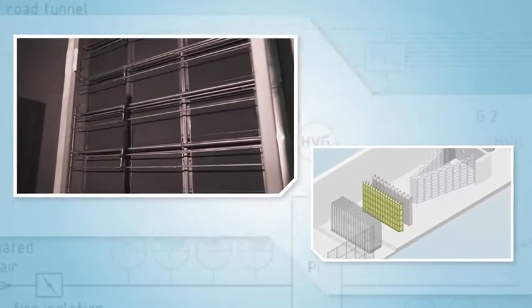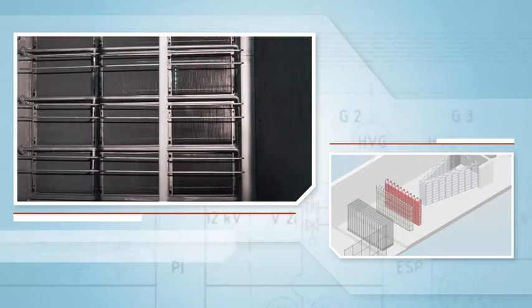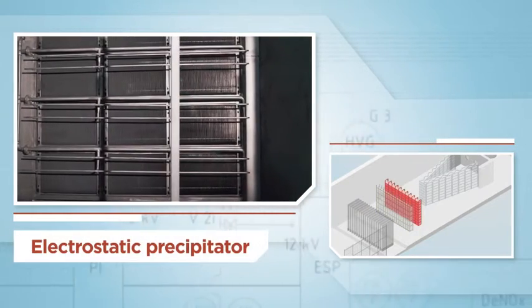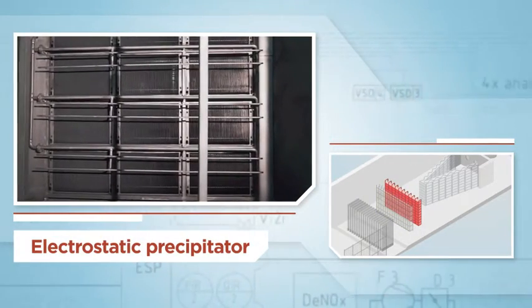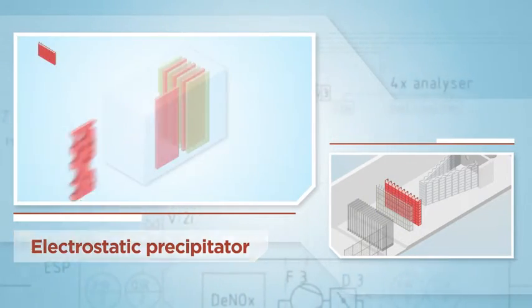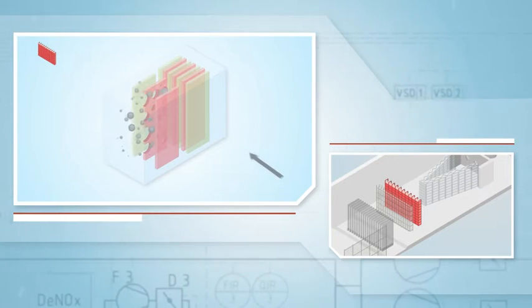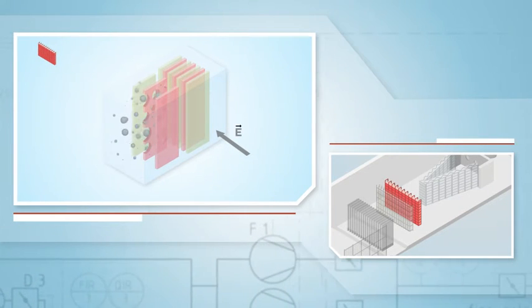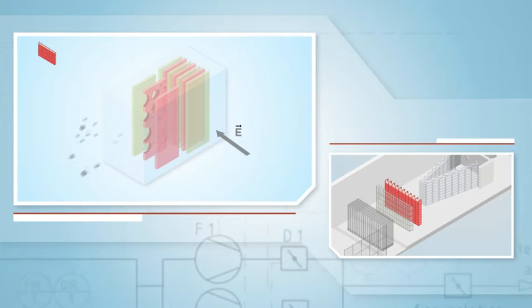The core element of the filter is the electrostatic precipitator, composed of an ionizer and a collector plate that capture the particulate by electrostatic attraction from a direct current electricity field generated by a high voltage transformer.